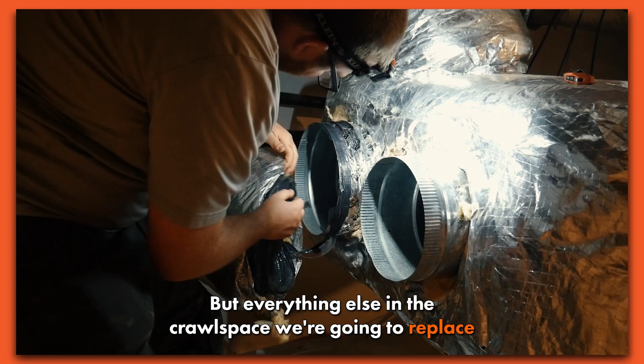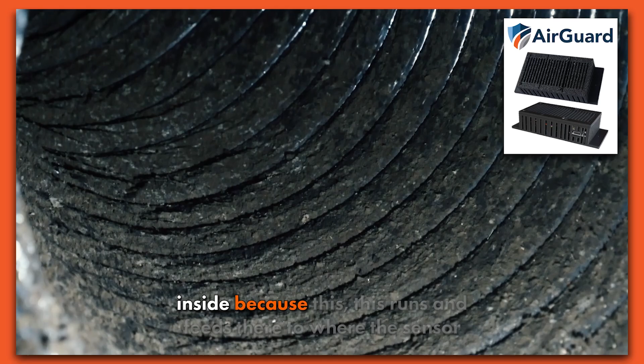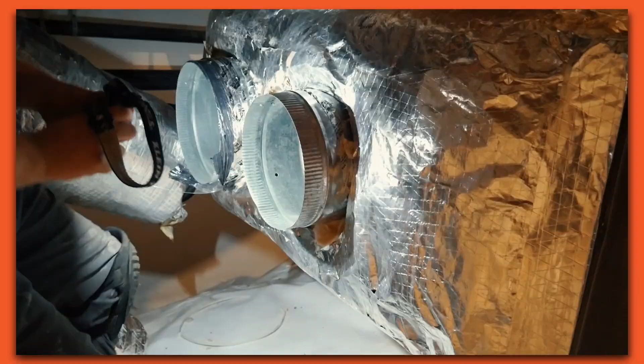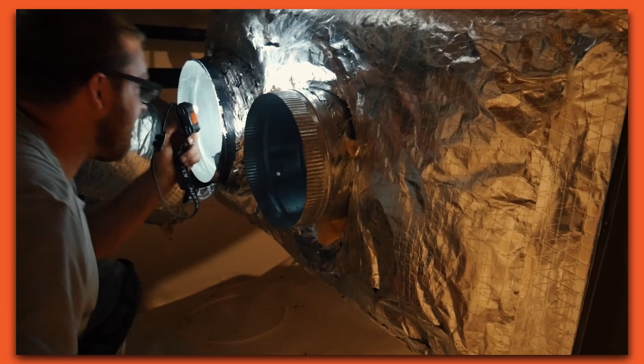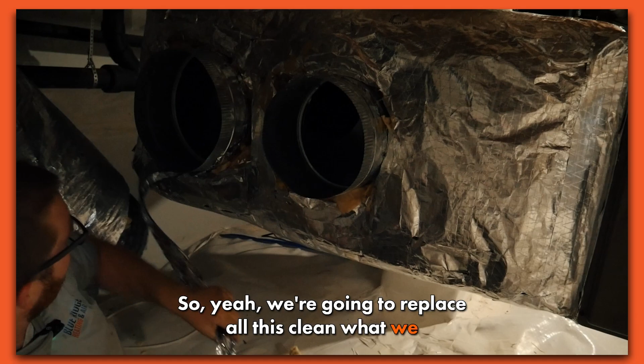Clearly the mold is off the charts here, which validates the sensor that was triggering inside, because this line feeds air to where the sensor was. It's picking up all of this growth, and that's just not good. So we're going to replace all this and clean what we can.